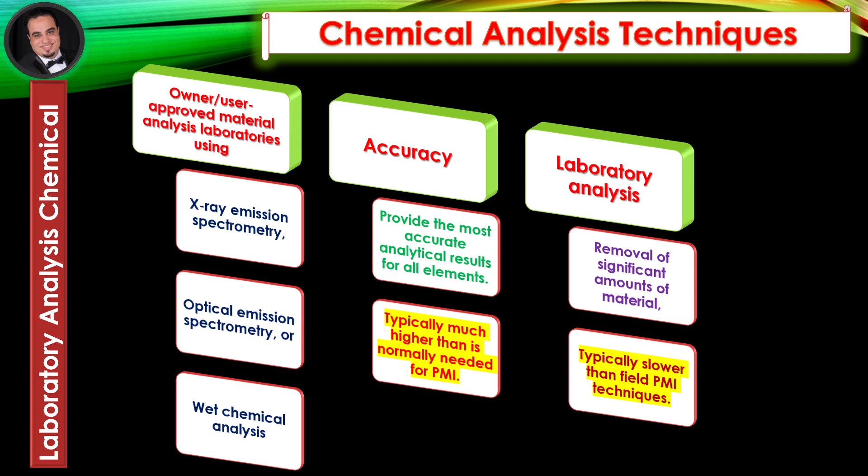Chemical Analysis Techniques: Laboratory Chemical Analysis. Owner-user approved material analysis laboratories using X-ray emission spectrometry, optical emission spectrometry, or wet chemical analysis can provide the most accurate analytical results for all elements. The accuracy is typically much higher than is normally needed for positive material identification. Laboratory analysis may involve the removal of significant amounts of material and is typically slower than field positive material identification techniques.